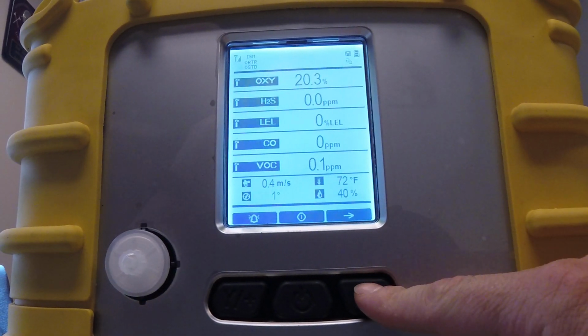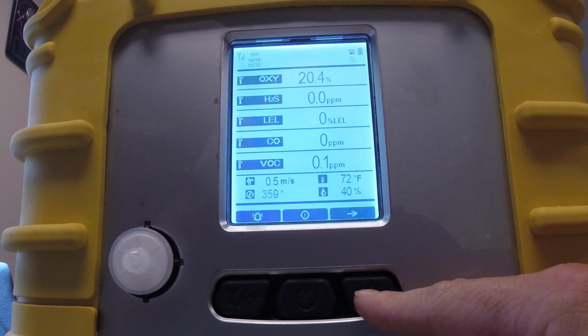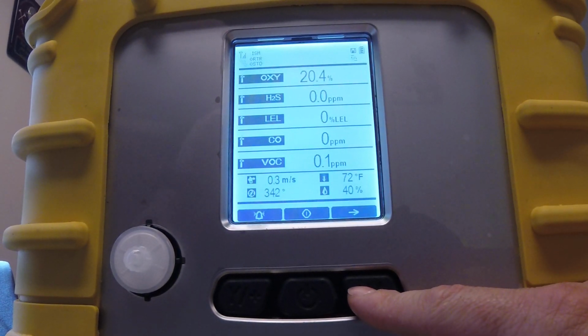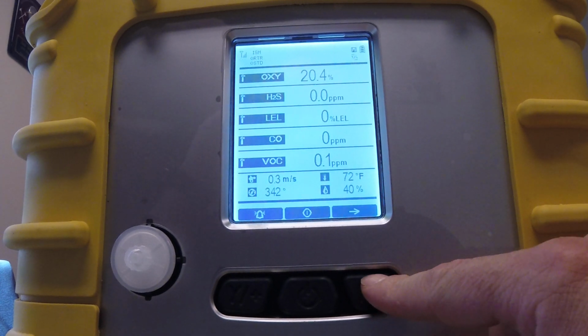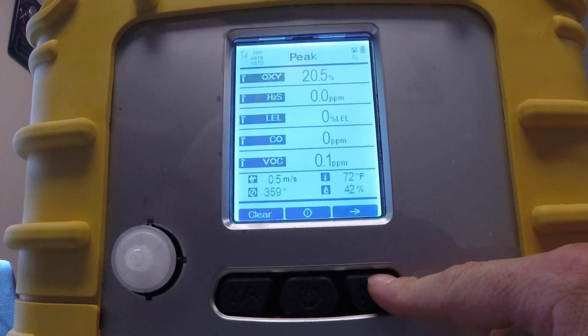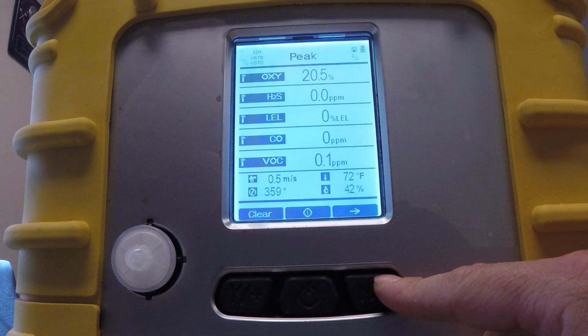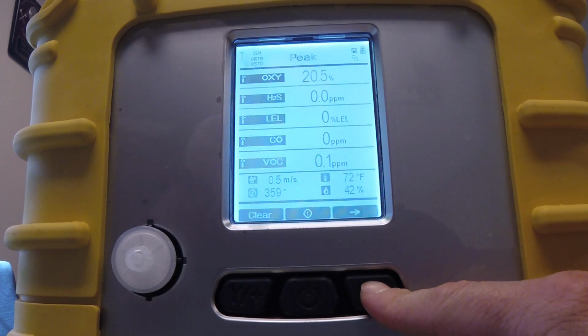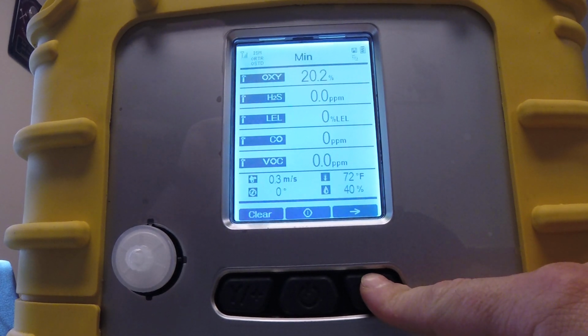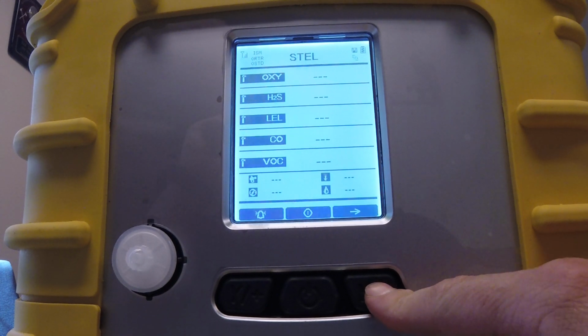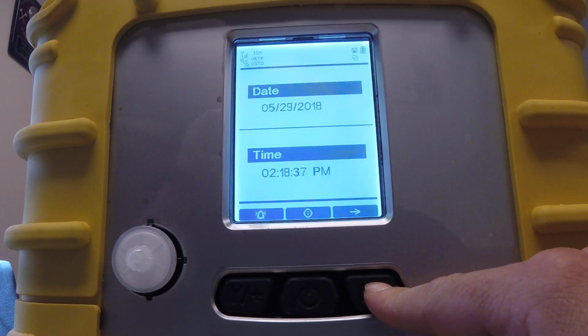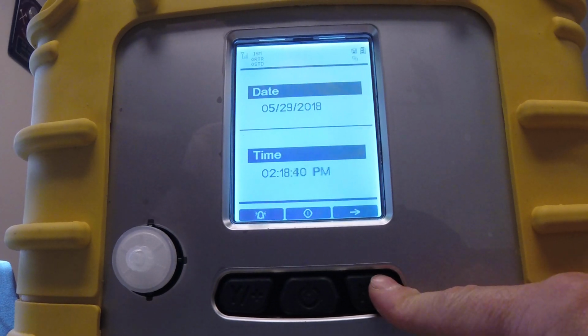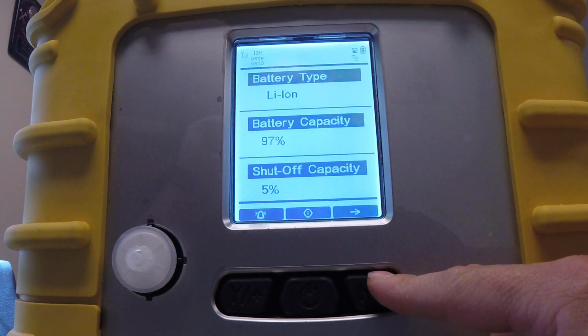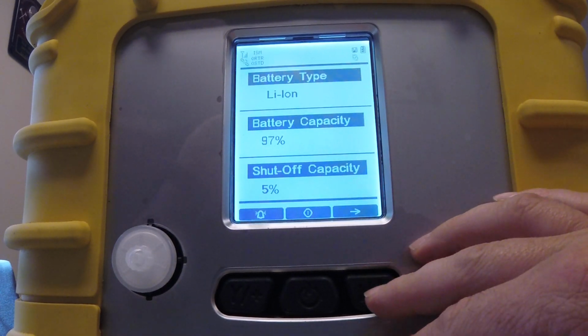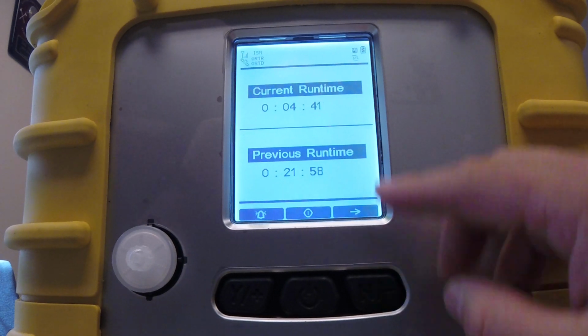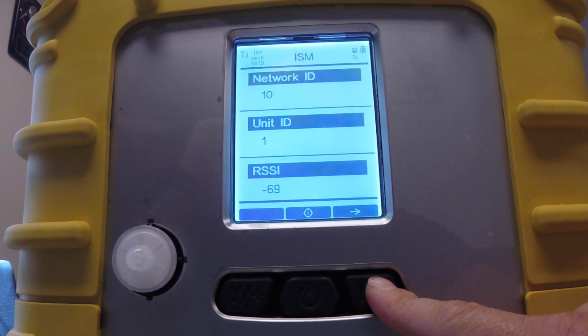So we're just going to go through the screens and some of the main functions that, for all intents and purposes of this training, are what we're going to hit on for now, and we'll get more in depth when people can get their hands on it. It's a little more easily explained. So a screen that's reading what our peak values have been since we turned it on, minimum values of what it's read since it's been turned on, short-term exposure limits, time-weighted average, current date and time, type of battery, battery life left. At 5%, this will automatically shut down and preserve data. Our current runtime, how long it ran the last time we turned it on.